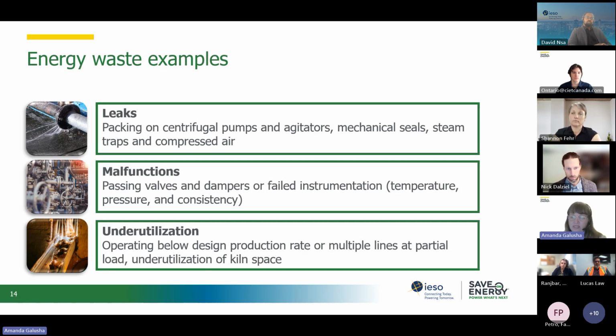Malfunctions may seem like an easy one to spot, but there are likely some issues that just never get around to being fixed, or things like actuators that people assume are working and being controlled, but never actually check to make sure they're working properly. Those are some of the gaps we're talking about with malfunctions.